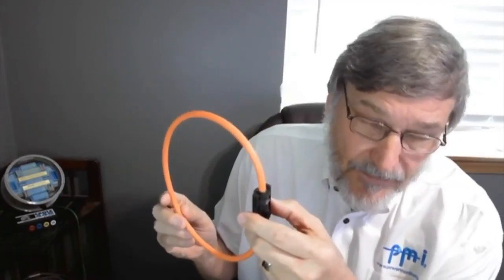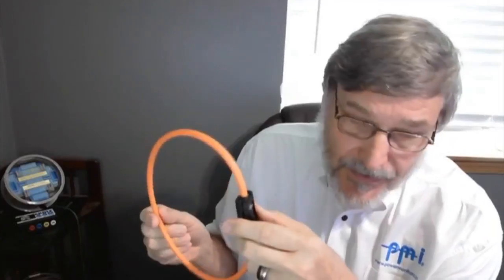Also, the Flexi T's have a 100, 1000, and 5000 amp ranges that you can set. There's a 1% accuracy at each of those ranges. But if you really need to record, say, half an amp, you can double wrap these and it'll pick up lower amperages. I'll show you in Provision where you can adjust that too. And whoever you give the recording to, you need to make sure that you tell them that you double wrapped the Flexi T's.